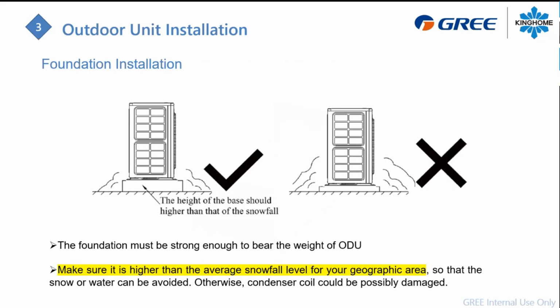Again, make sure the system is higher than the average snowfall in your region. Here in Quebec, everything is higher than 20 inches. So make sure the snow will not block the condenser in any way. So you need to provide a rack high enough to manage the defrost, the water coming from the units, and also the snow level. We're gonna see how these units work.